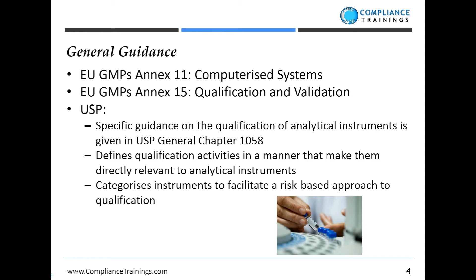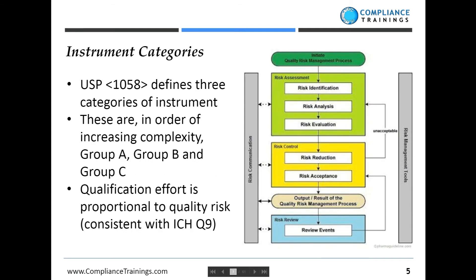For that specific guidance we turn to the United States Pharmacopeia, which has a really useful general chapter — General Chapter 1058. That gives us a really nice framework on which to plan qualification activities based on a categorization of instruments in terms of their quality risk. This USP general chapter defines three categories: instrument group A, group B, and group C, and the qualification effort in each group is related to quality risk.